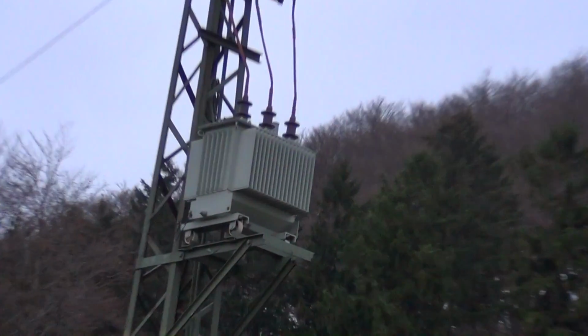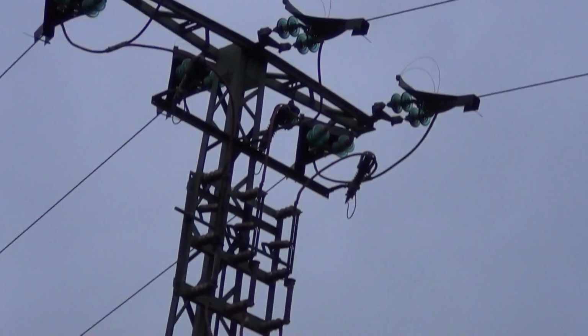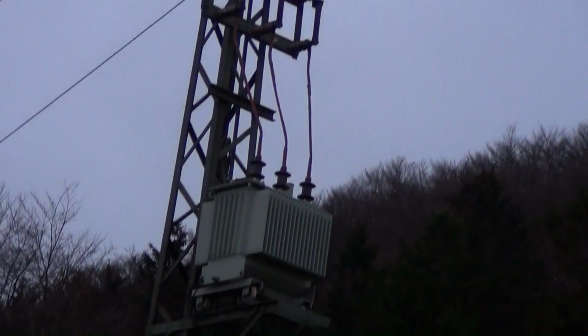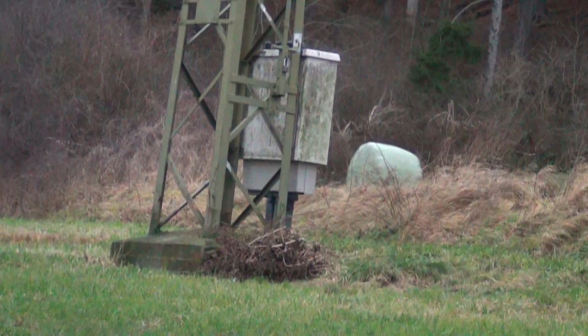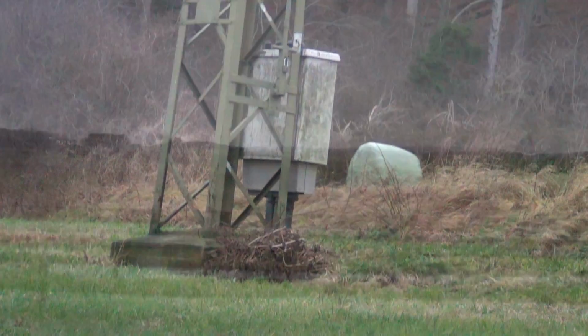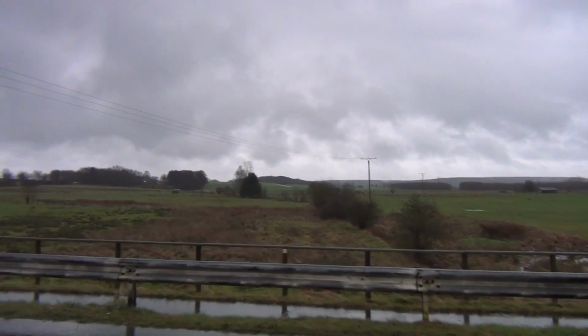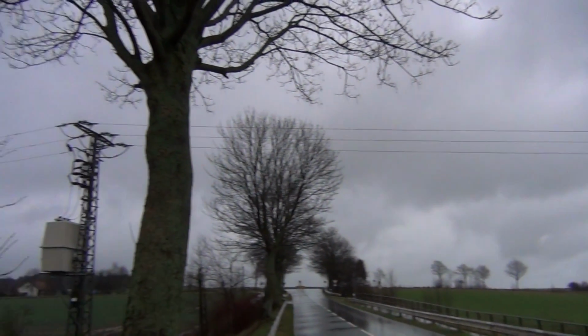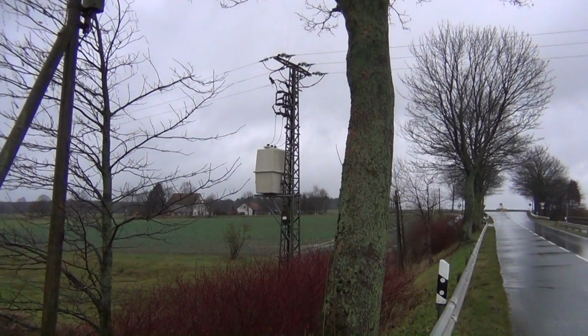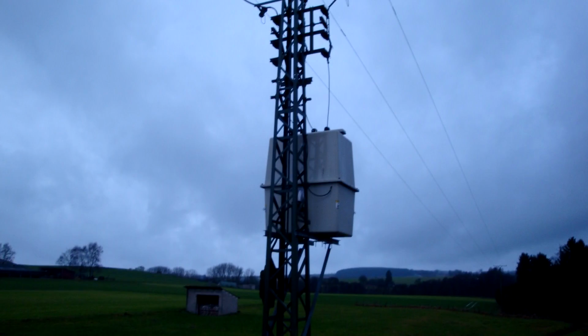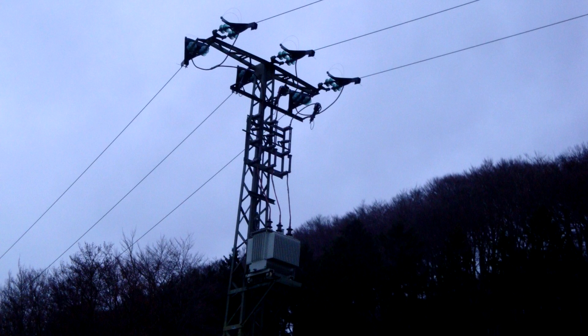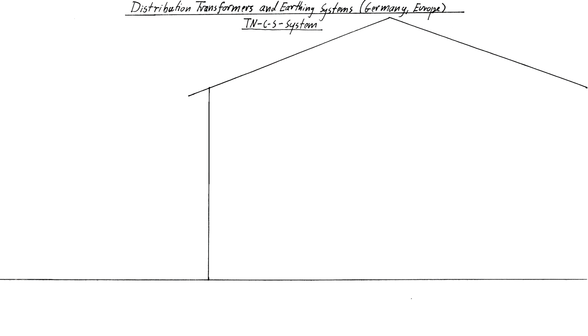Right here, you see a distribution transformer mounted on a pole. The three phases of the medium voltage grid can be seen up in the air, while the 400 volt line is implemented as an underground cable right here. And here you see yet another medium voltage line and another distribution transformer which feeds some local houses. These distribution transformers are particularly interesting for us, because they are directly involved in answering the questions we had about the little neon tester.